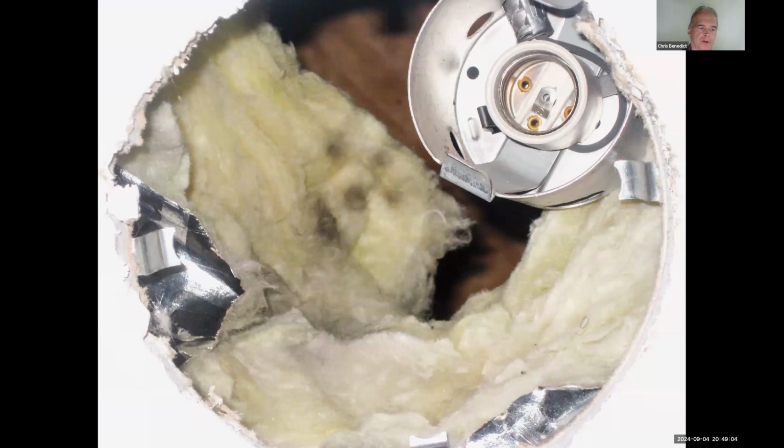So here's fiberglass in the ceiling, and you see the 5 dirt spots. They correspond to the 5 holes in the back of the electric box, the light fixture box there that got moved out of the way. So this shows that lots of air moves through light fixtures. It used to be that at Home Depot you could special order light fixtures that were airtight. I think they stock them now. Last I checked, the hi-hats that go recessed in the ceiling, you can buy them airtight. But usually people don't bother, so air's leaking all over the place.